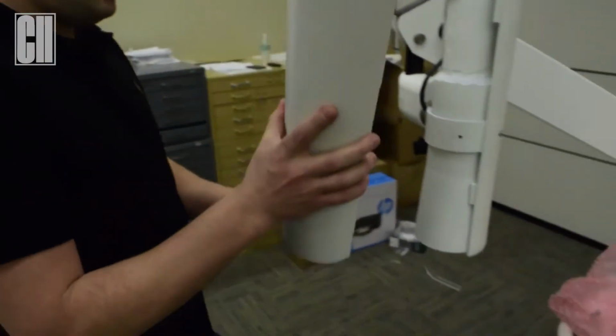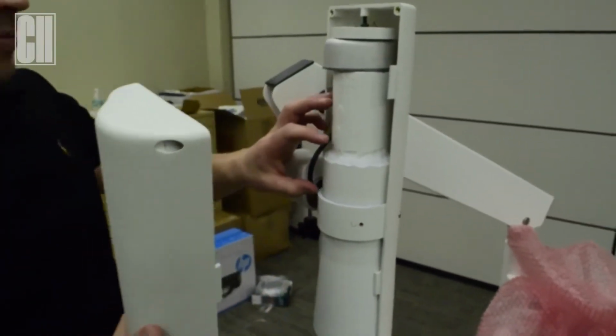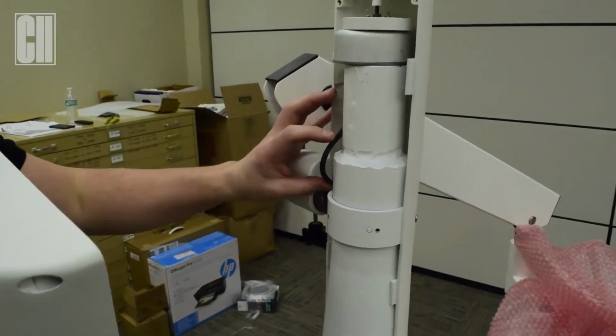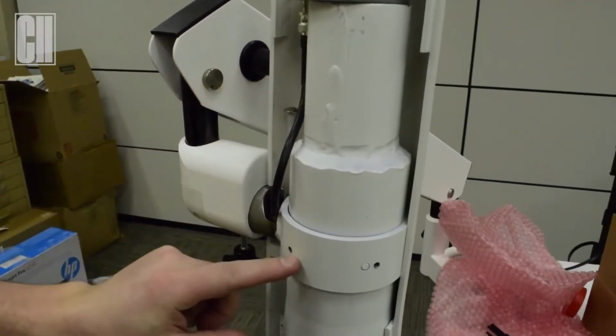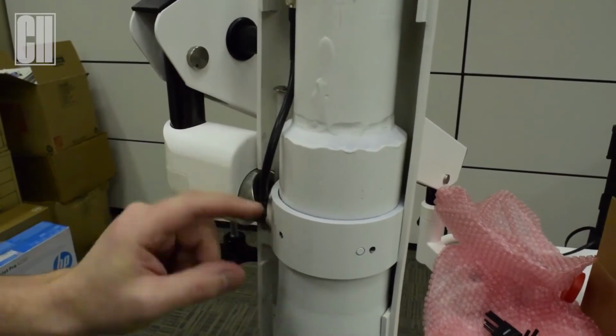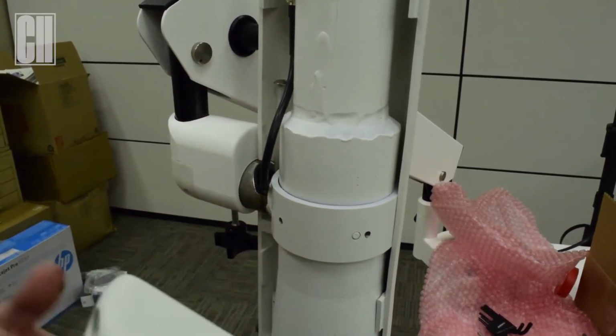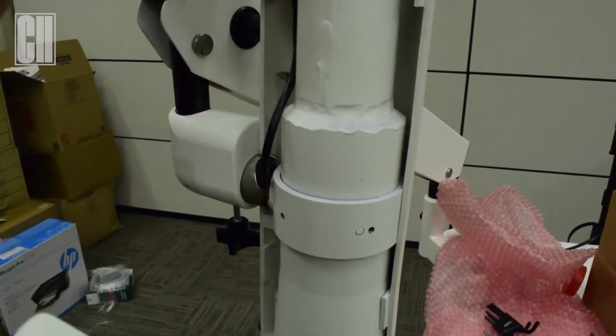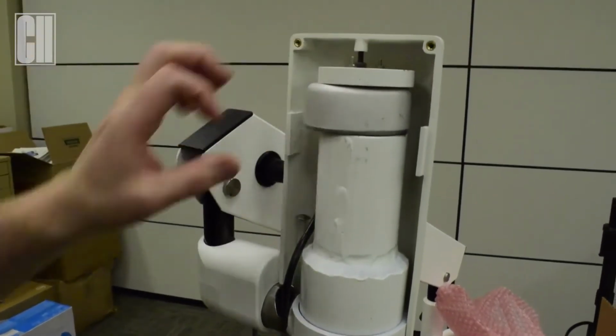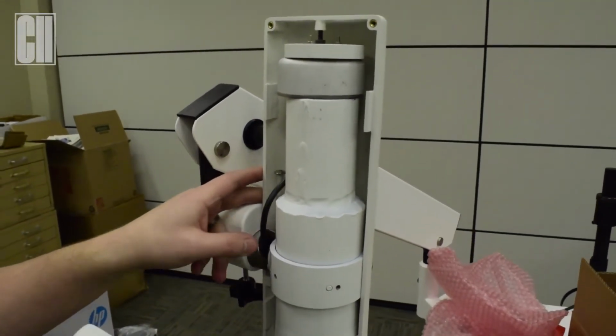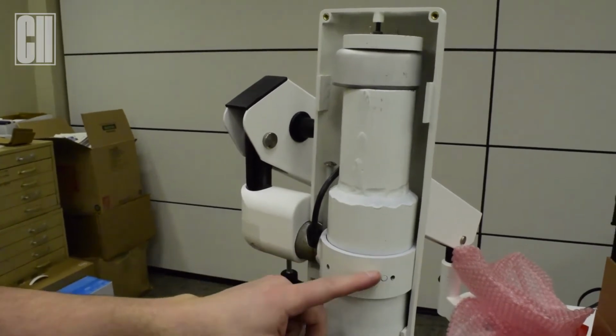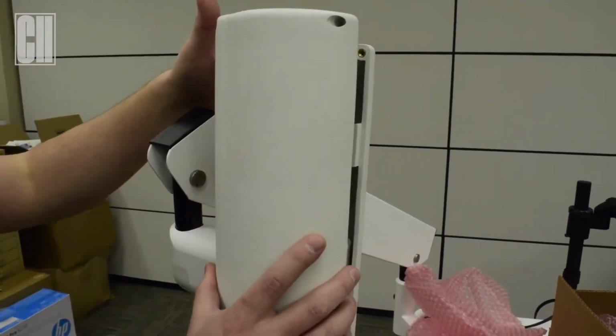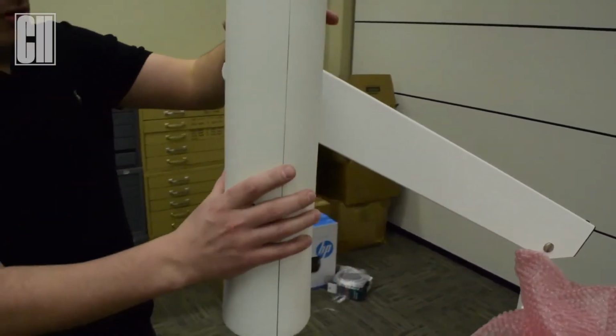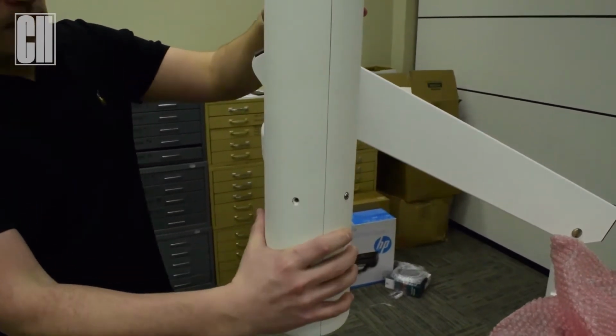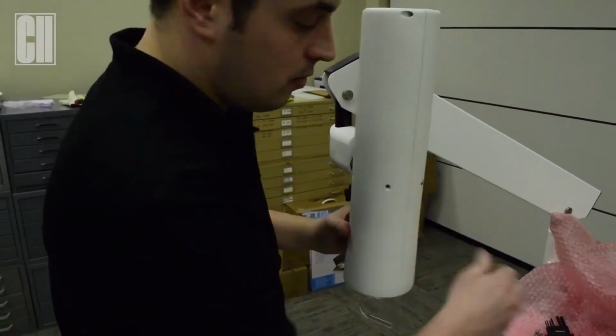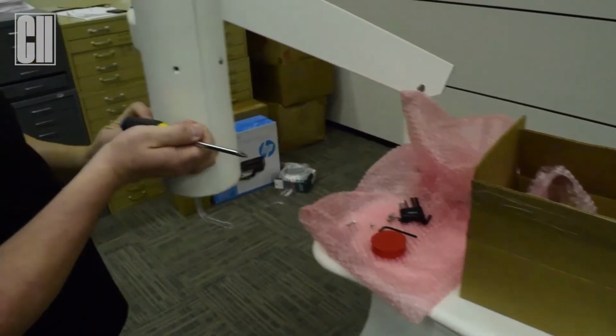We grab the other side. You want to make sure, if the cable is a little longer, that it's out of the way and not hanging down covering this up, as it will cause it not to line up exactly. So the best thing to do is gently twist it a little. Try to push it a little out of the way, that's fine, as long as it's not down in this area. Once you get that lined up, you put in the other 2 Phillips head screws.